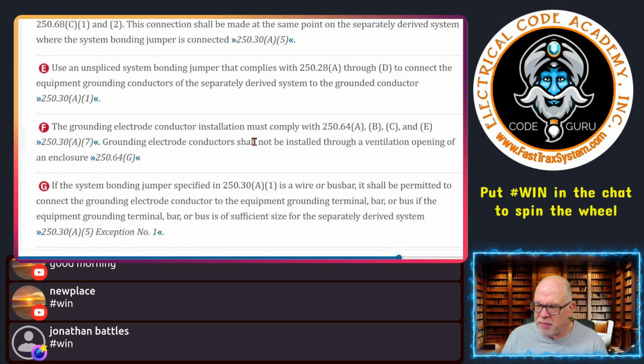The installation must comply with 250.64(A), (B), (C), and (E), and 250.30(A)(7). Okay, so the grounding electrode conductor shall not be installed through ventilated openings and enclosures. So that's another aspect of it. So we have to meet the rules.